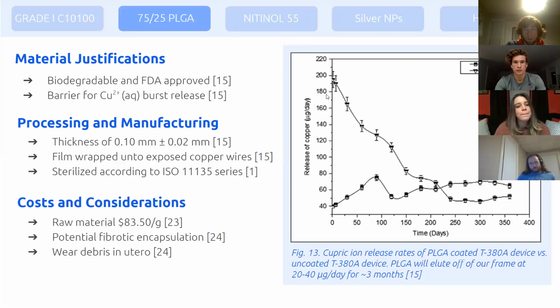To address what burst release is and how our device will account for it, we look to a 2015 study which investigated such occurrences in vitro. The IUD working range requires cupric ion release between 20 to 80 micrograms a day, and the patient should not experience high bleeding and cramping relative to their baseline during this time. However, during the first 3 to 6 months after implantation, elution rates can be upwards of 200 micrograms. The 75-25 PLGA functions like a sieve, where an appropriate amount of copper ions are released from the device to ensure functionality, but not so high that the patient experiences discomfort.